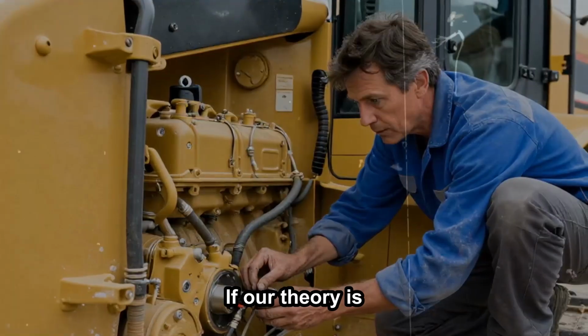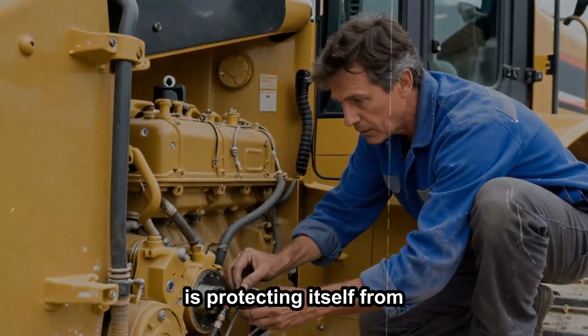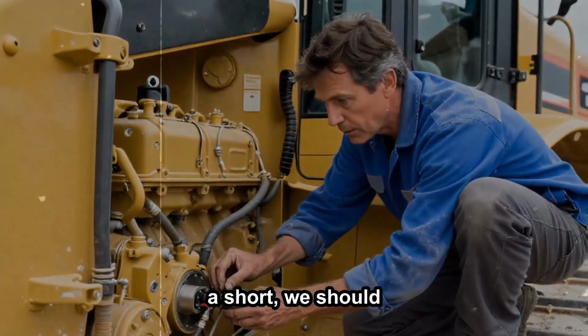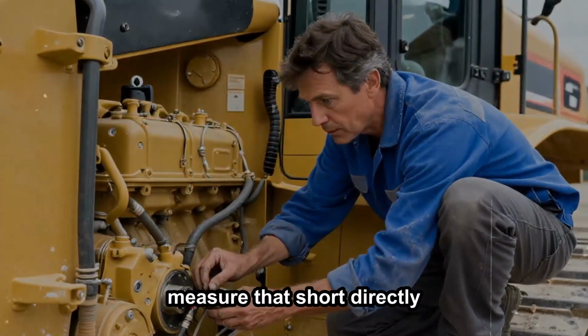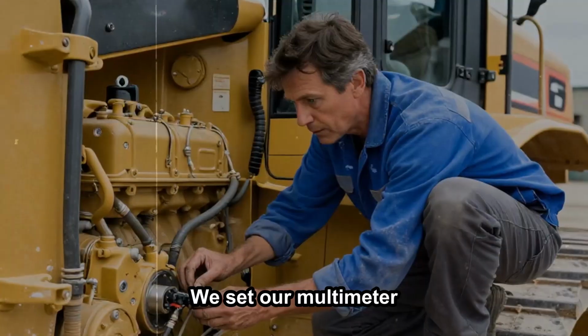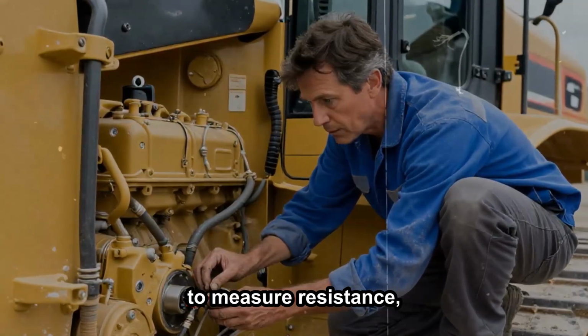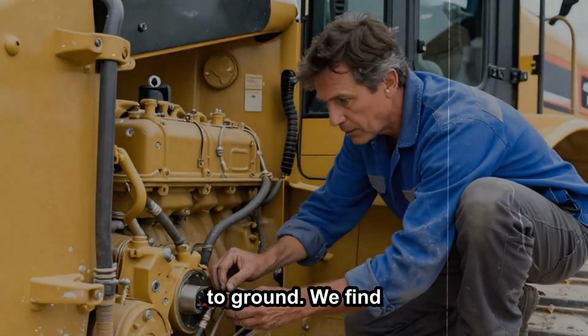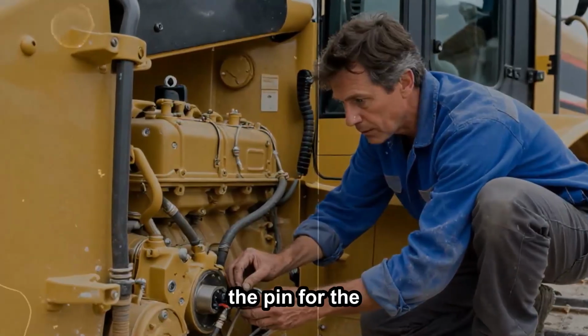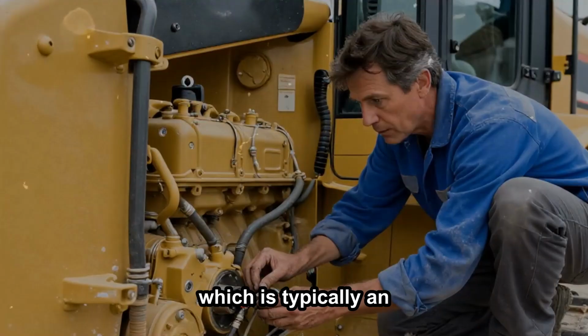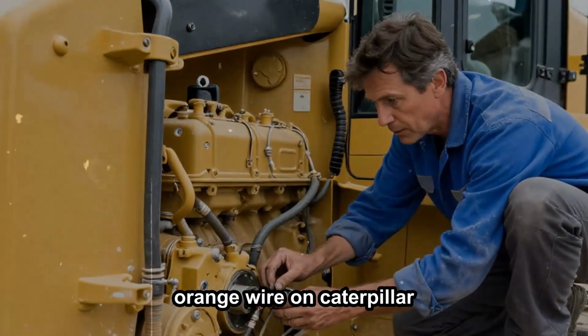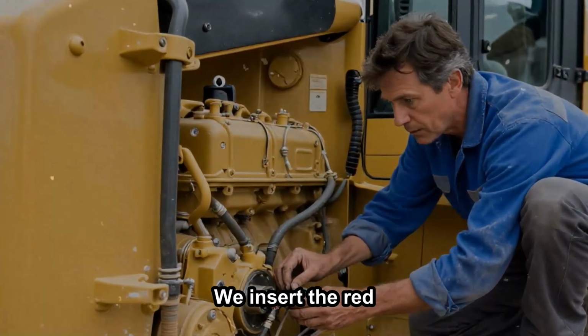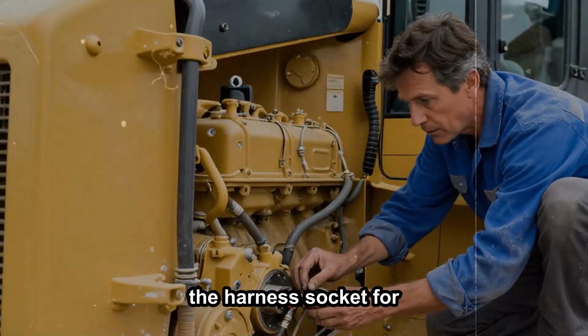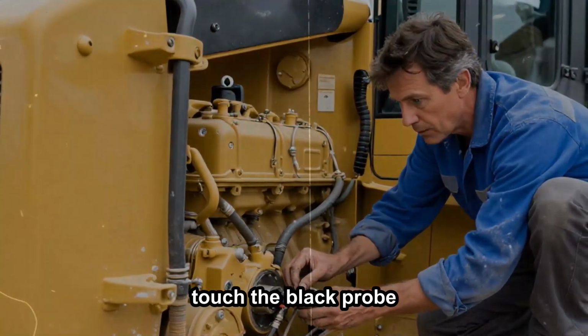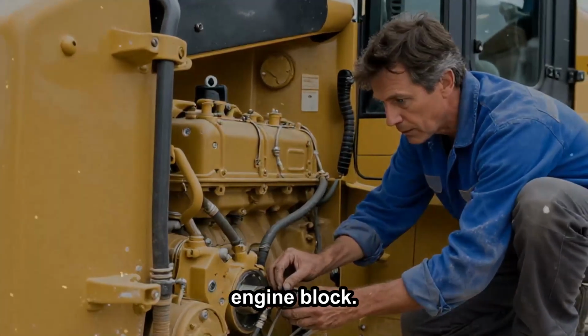If our theory is correct, that the ECM is protecting itself from a short, we should be able to measure that short directly at the harness connector. We set our multimeter to measure resistance, specifically looking for continuity to ground. We find the pin for the sensor supply voltage, which is typically an orange wire on Caterpillar schematics of this era. We insert the red probe into the harness socket for the sensor supply and touch the black probe to the cast iron engine block.